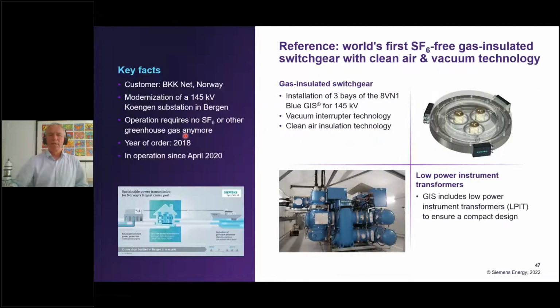This is a picture of the first 145 kV vacuum interrupter and clean air technology. We call that blue technology. So why is it blue? We call it blue not just for marketing issues. We called it blue because if you buy clean air, the color code of the gas bottle is usually blue. And we took that color code of the gas bottle and used it to also symbolize that in that gas insulated product, there is only clean air in.